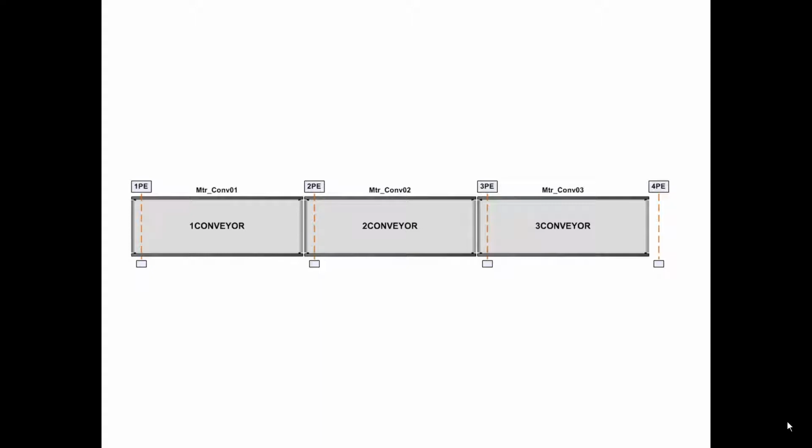Following a system stop, we do not want the conveyors to be running with a subsequent system start. So if any conveyors are running and you do a system stop, not a conveyor stop, but a system stop, all conveyors are going to stop. If you do a system start, we don't want the conveyors that were running before the stop to start up again. Each conveyor will have a unique rung of logic to start and stop them if the system is enabled.